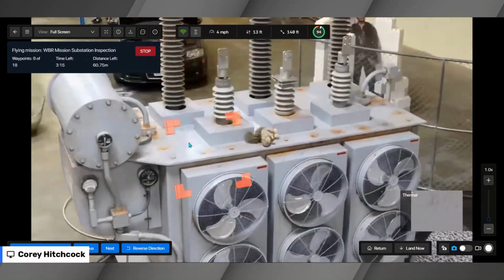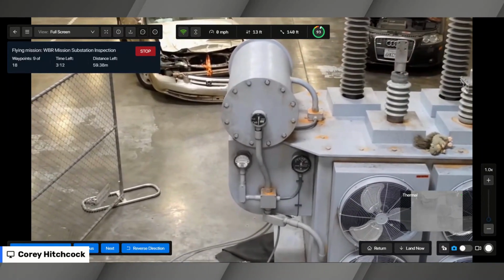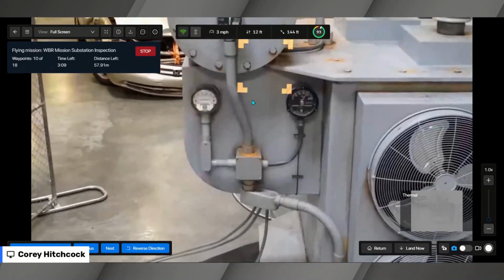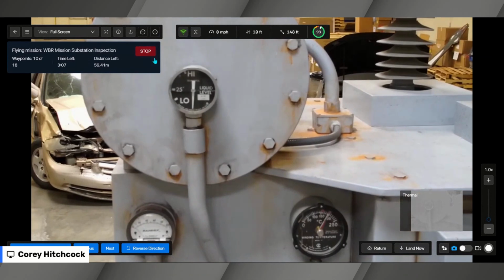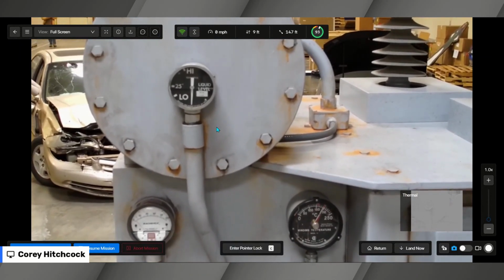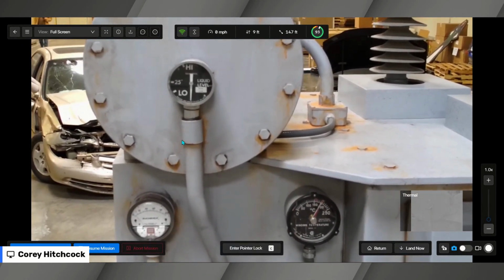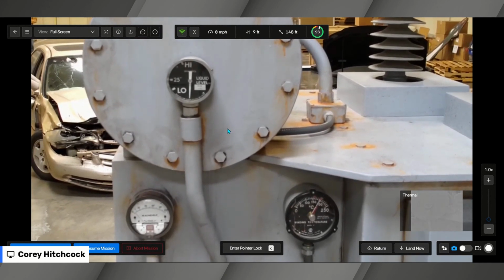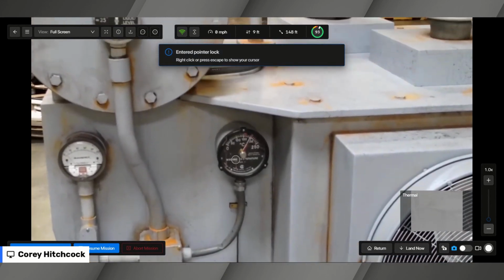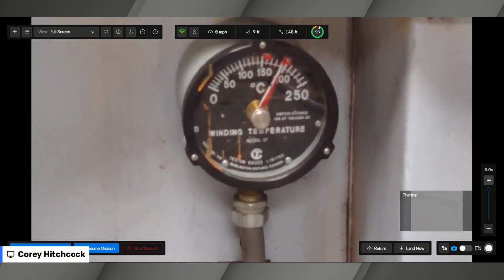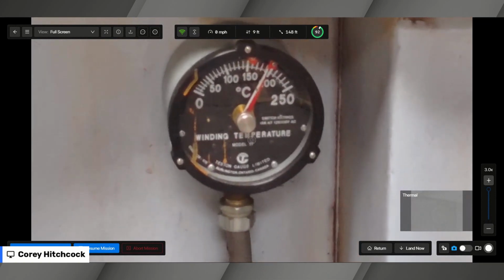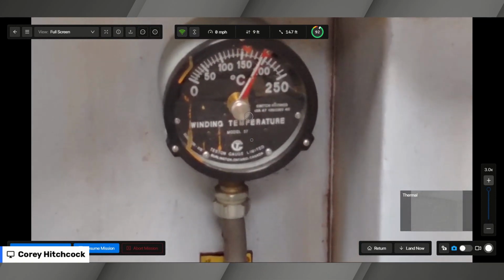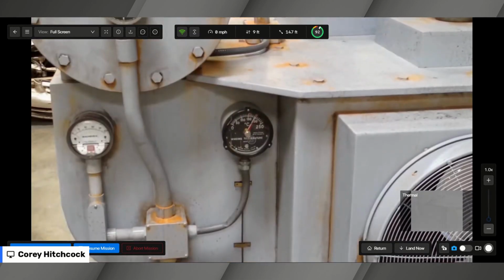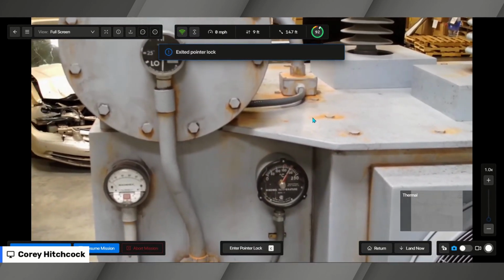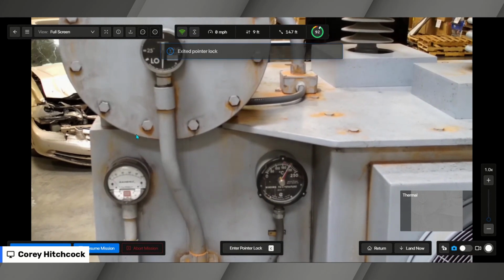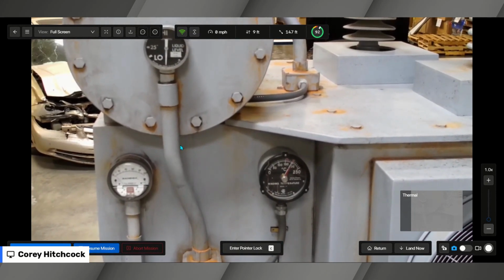We're going to move to check the other gauges and components on this power transformer. From this location, I can see that my oil expansion tank is pretty low. And it looks like my winding temperature is high enough that the fans should be running, and they're not. It's at the upper limit for my internal winding temperatures, and my fans aren't running, so we might have to send somebody out to look at this one. But I'm going to go ahead and resume the mission and keep it going.